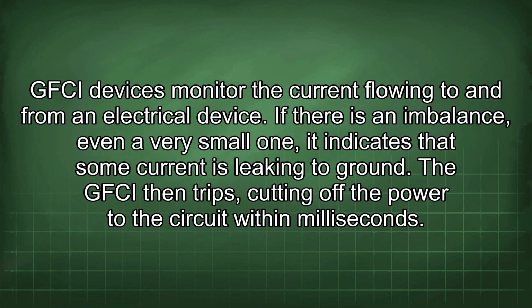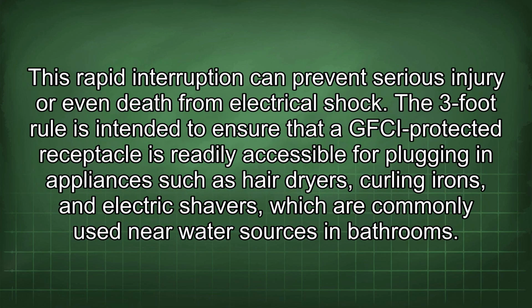GFCI devices monitor the current flowing to and from an electrical device. If there is an imbalance, even a very small one, it indicates that some current is leaking to ground. The GFCI then trips, cutting off the power to the circuit within milliseconds. This rapid interruption can prevent serious injury or even death from electrical shock.